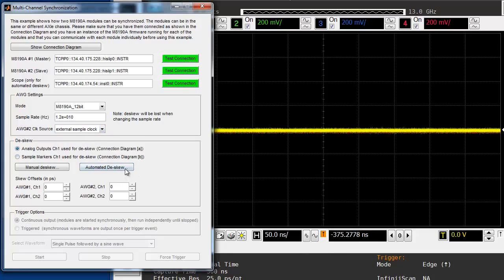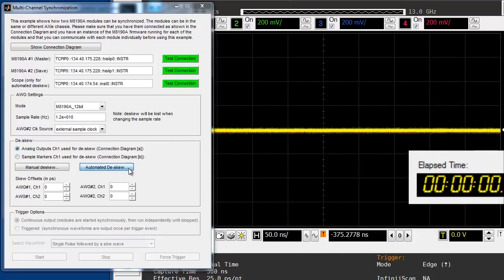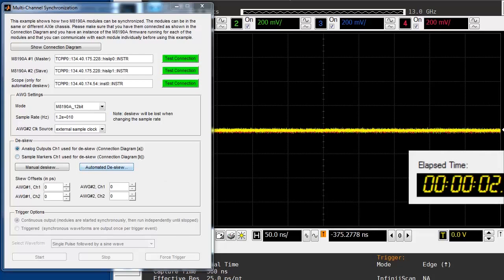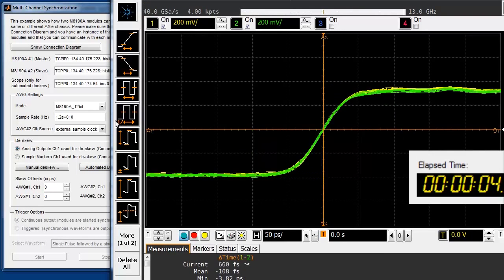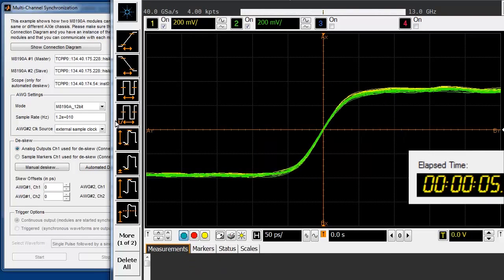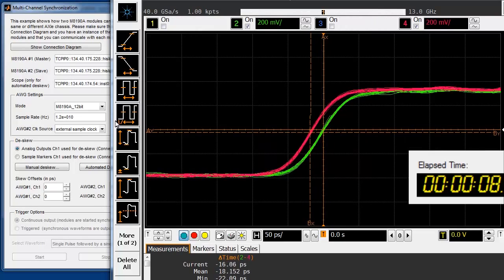By clicking on the automatic de-skew button, I can start the de-skew process, and as you can see, it only takes a couple of seconds until the four channels are aligned.